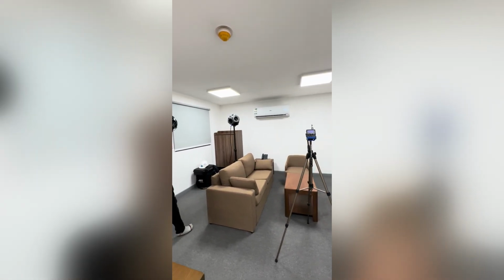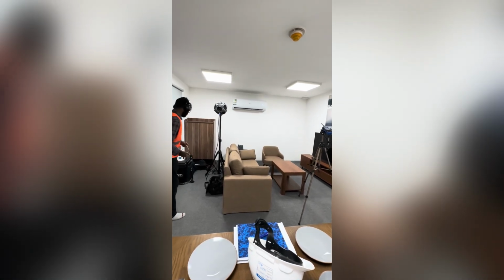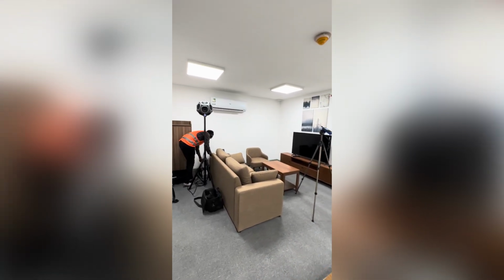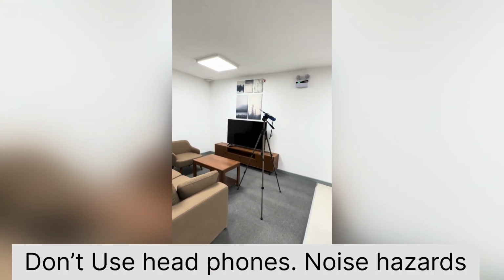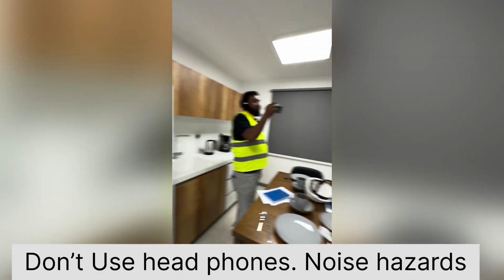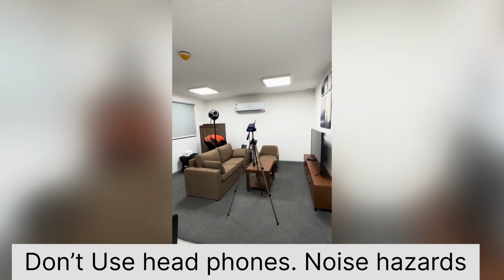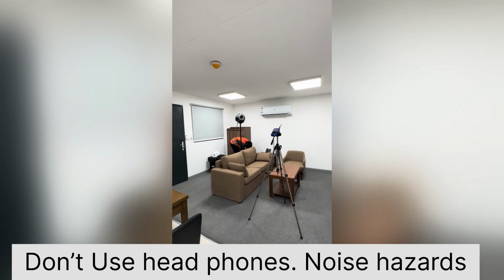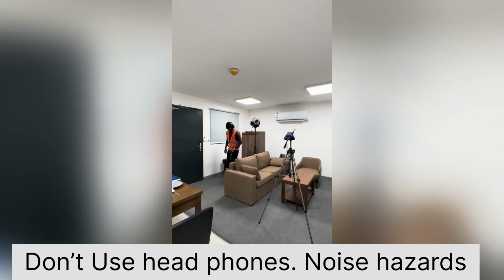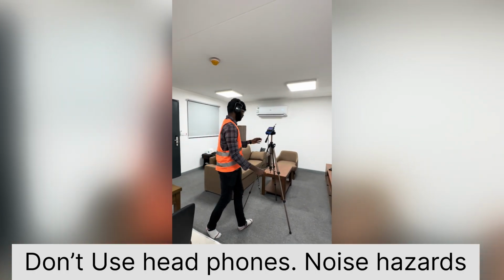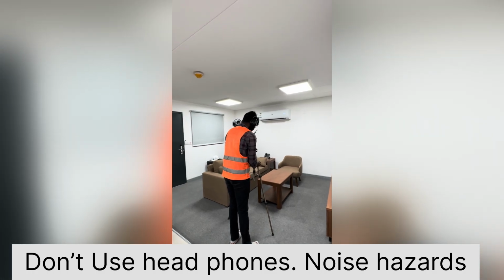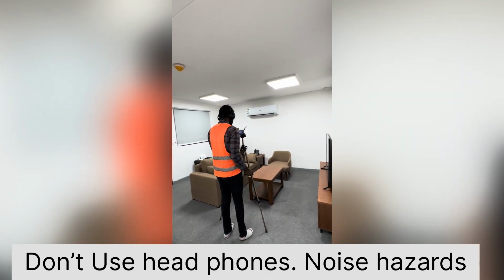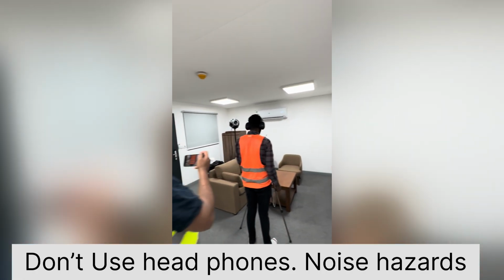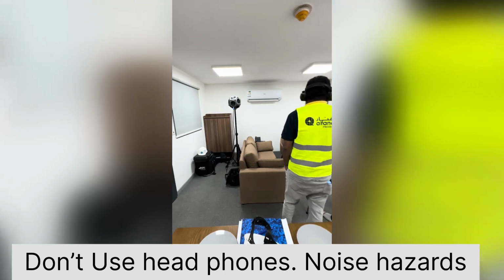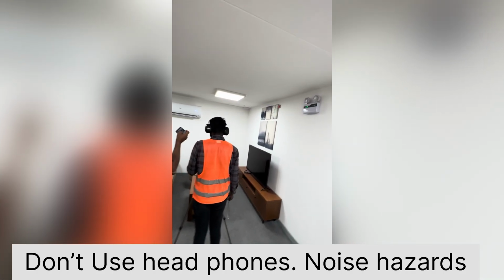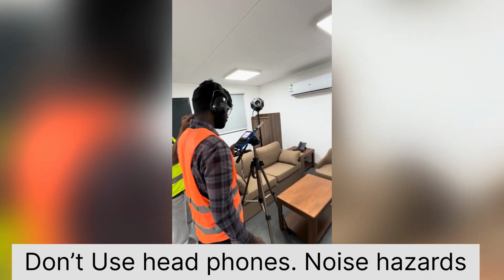Here you can see we are going to perform an acoustic test for the rooms. The purpose of this test is to check two things: soundproofing and sound insulation. For soundproofing, there is a criteria called NC, noise criteria. For sound insulation, there is STC, sound transmission class. The maximum value of NC should be less than 35. If it goes more than 35, there will be much more disturbance by sound in this room, so we have to keep the criteria down to 35. How we keep it down, I will also explain.